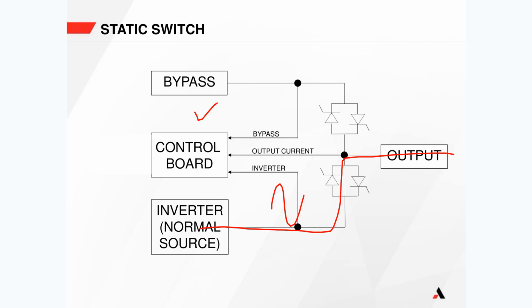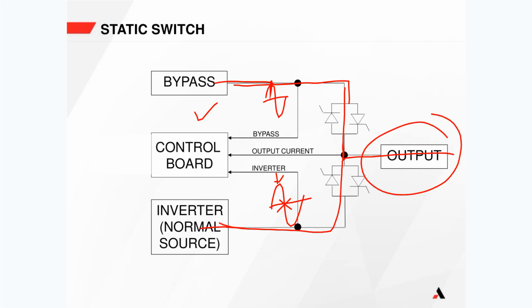we've got a sine wave going through there. Let's say they switch to bypass at exactly that point there. Then our bypass static switch is going to turn on at exactly that point there. And because they are in sync, remember, you cannot switch an SCR off until it gets to this zero crossing point. Remember that? So what you're going to have is the bypass and the inverter are going to be supplying the output for this portion of the sine wave until we get to this zero crossing point. And then when you get to that zero crossing point, this SCR will be told to turn off and this will remain on.